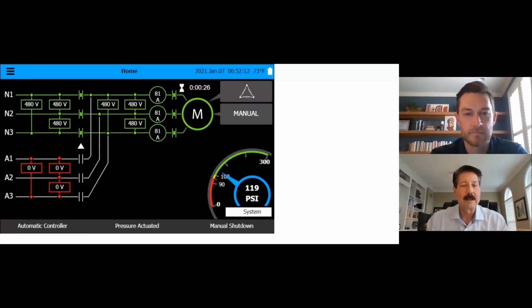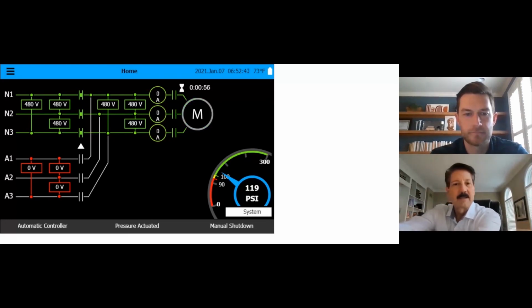We get calls from time to time where people say, hey, the pump starts by itself, and we'll have one of our authorized service providers go out to the field, and they see this and they go, all right, let me look at the data. And they'll call the gentleman over and say, let me show this to you. This is not starting by itself. It's manually started. It's telling us how it started, obviously. Someone has to come in that room, press that green start button for this to be in a manual mode. Again, if I stop it and start again, manual mode.